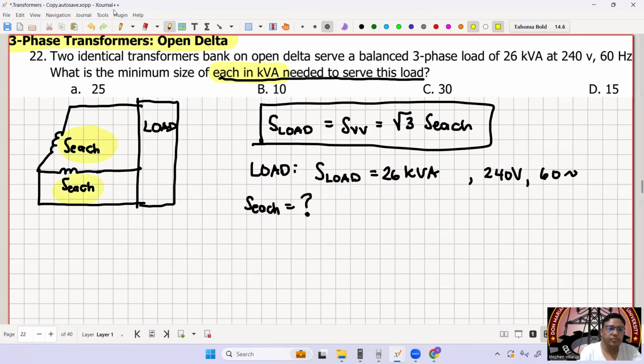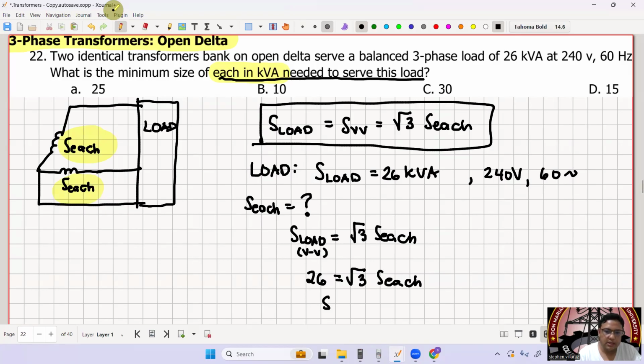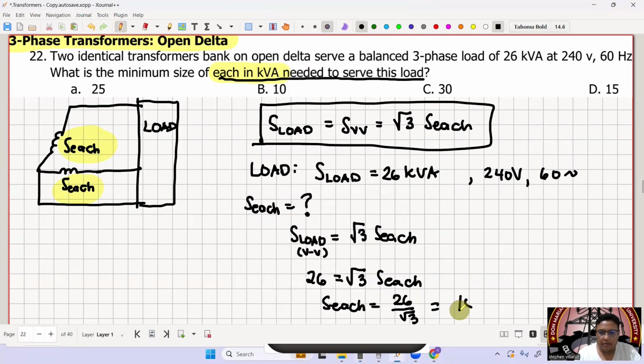Okay, ito. So therefore, kunin natin yung SH. So this is now S load in open delta or VV. So this is now square root of 3 times SH. So therefore, 26 is equal to square root of 3 times SH. So SH now is equal to 26 over square root of 3, or ilang kVA ito? So 26 over square root of 3, this is 15 kVA. And this is letter D. Okay? Letter D.